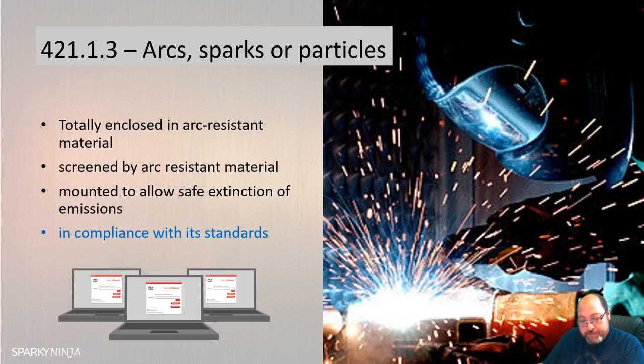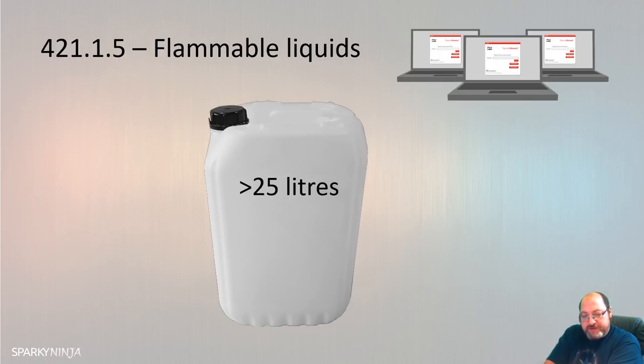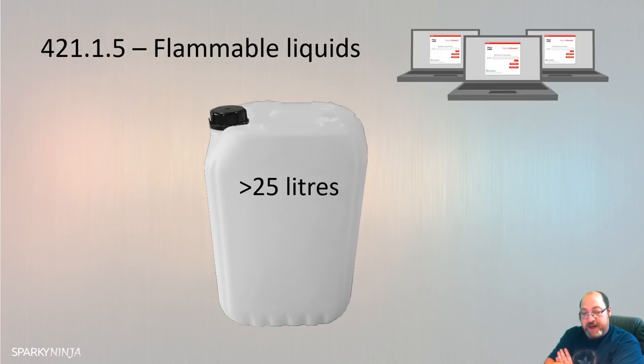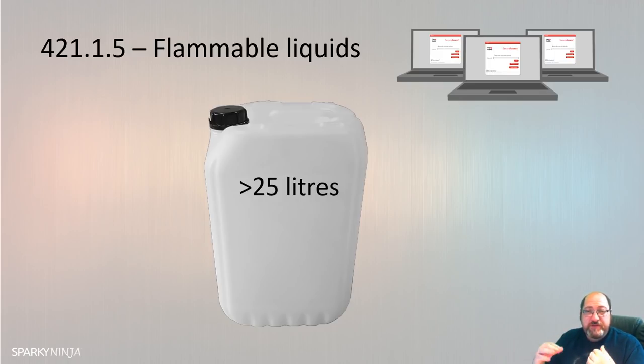Regulation 421.1.5: if equipment in a single location contains a flammable liquid in a significant quantity, there'll be a need for adequate precautions to prevent any spread of this liquid, flame, and products of combustion. The generally accepted lower limit of a significant quantity is 25 litres — so this regulation really needs consideration if we have 25 litres or more of stored flammable liquid within our electrical equipment.